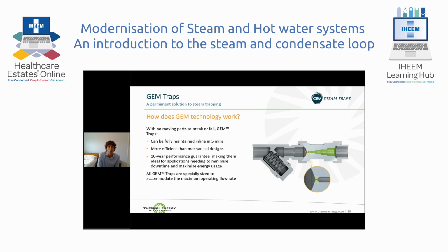There is a solution. The GEM trap is a permanent solution to steam trapping. It has no moving parts. Its performance is guaranteed for 10 years. It's very easy to maintain. Full maintenance can be conducted in line within 5 minutes, as long as isolation can be achieved, and there's no or minimal requirement for spare parts. It's also been demonstrated in both field testing and laboratory testing to be more efficient than most mechanical steam trap designs.